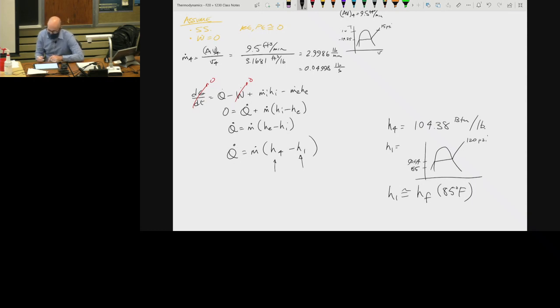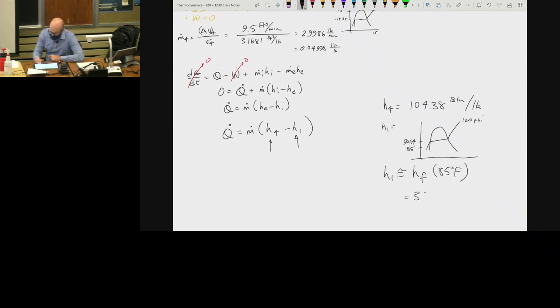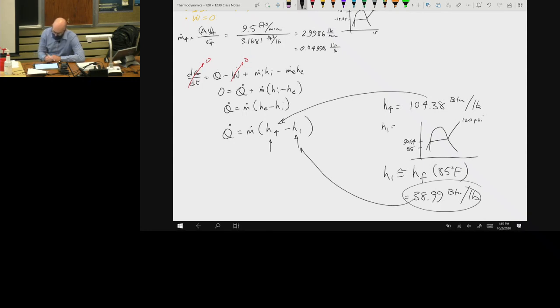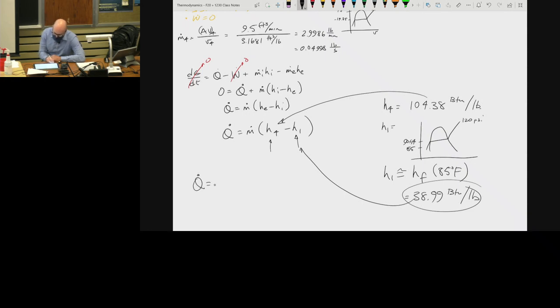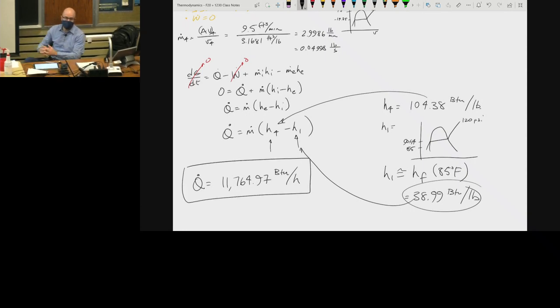The liquid approximation, that's equal to 38.99 BTU per pound. Now I can plug these things in, plug this into here and this into here. With my mass flow rate, I found that my heat transfer is going to be 11,764.97 BTUs per hour. That's how much heat must be added to the system for this refrigeration cycle to work.